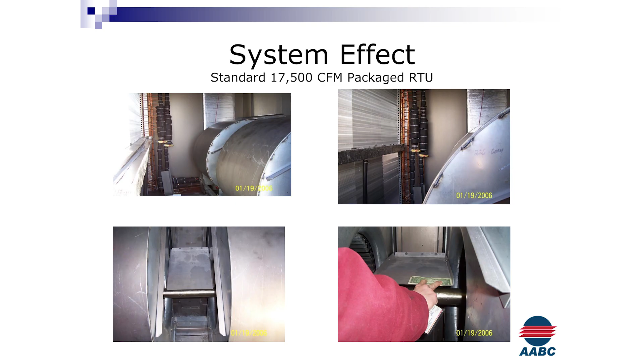The unit's running fine. It's not bouncing. The roof's no longer in danger. People can go back in the building. This was bouncing so bad that they were scared to send people into the building. So again, if you have a really good test and balance firm that you can rely on and ask specific questions, this is the added value of a TAB firm that really cares about the process and cares about the sustainability and the serviceability of the equipment after they leave.